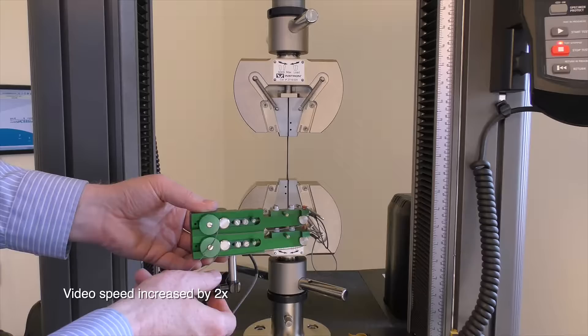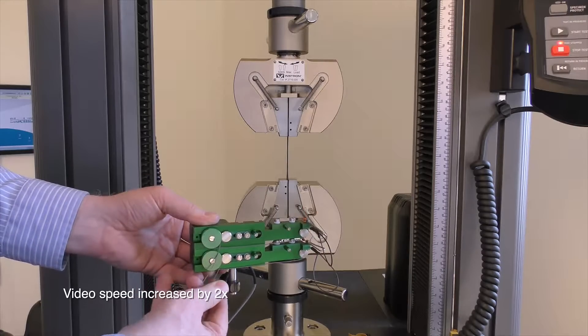Install the Model 3800 extensometer's body on the adjustable magnetic base.